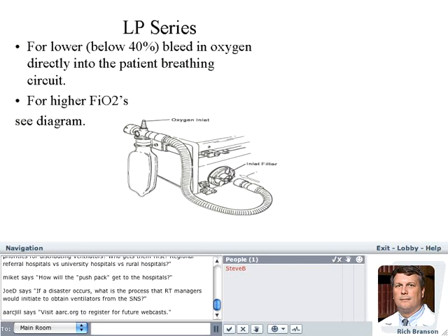For higher FiO2s, there's this system here, and what you're seeing is the back of the ventilator, the LP10, where the inlet filter is. And this system comes with the device from the stockpile, and you have a reservoir bag, and you see where the oxygen connects. And then it uses that bag as well as that tubing to fill with oxygen. And then when the piston draws in gas to deliver the next breath, it will draw in gas from that bag. And just to the left of the oxygen inlet there, kind of looks like a valve that you might turn. That's actually kind of an anti-asphyxia valve for the piston. If the piston draws in and the bag goes flat because the O2 flow is not high enough, it just draws in more room air, which decreases your FiO2.